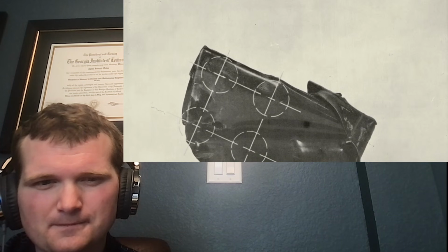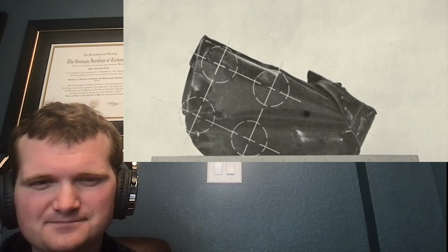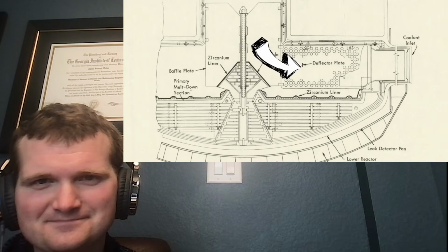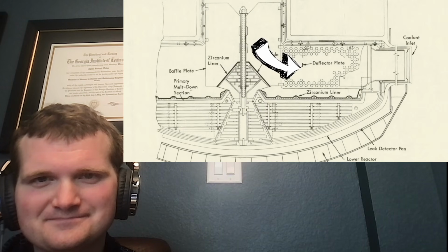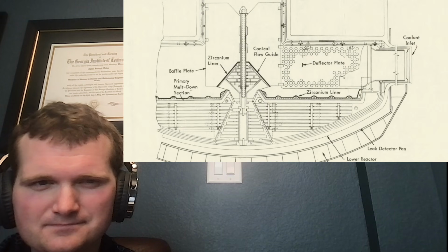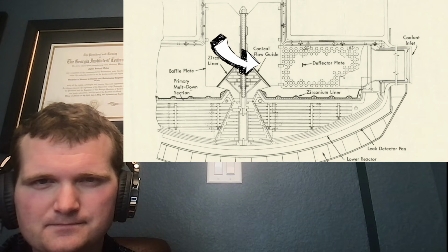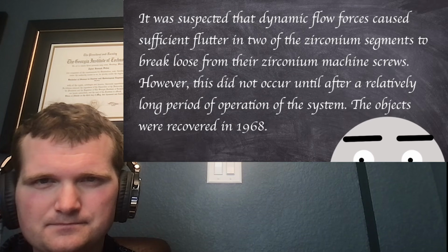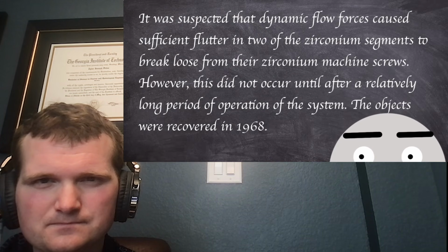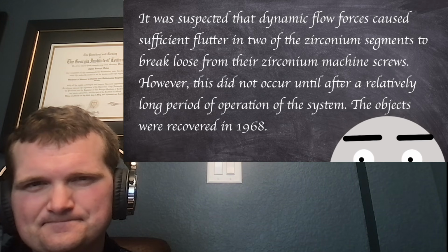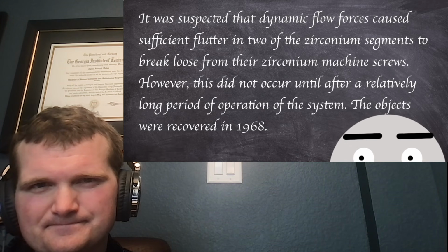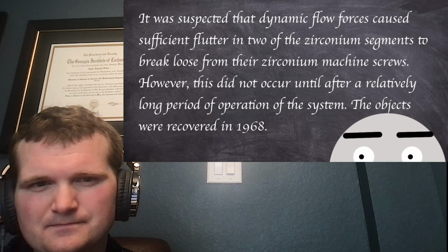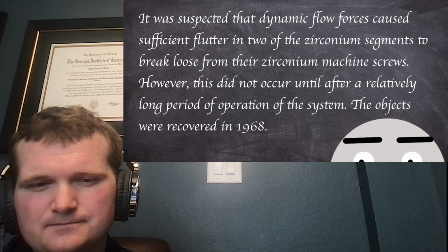This was discovered by draining considerable amount of coolant and the insertion of a borescope. The obstruction was part of 6 zirconium alloy panels used to direct coolant upwards to the reactor. It was suspected that dynamic flow forces caused sufficient flutter in 2 of the zirconium segments to break loose from their zirconium machine screws. However, this did not occur until a relatively long period of operation of the system. The objects were recovered in March 1968.